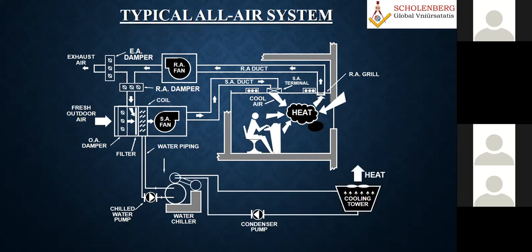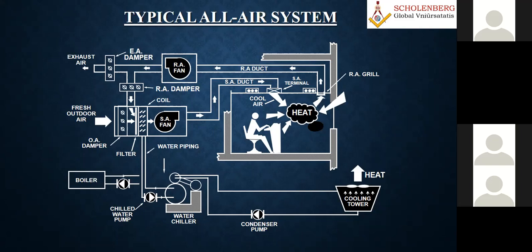The chiller can be water-cooled or air-cooled. If it's water-cooled, you have a cooling tower, which is another circuit I put in to show the whole picture. If you need humidification control, you need a boiler, so I've added a boiler here, along with a heating coil and humidification coil. This is the overall typical all-air system.